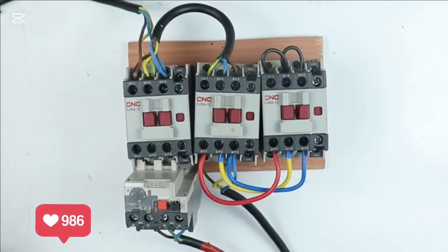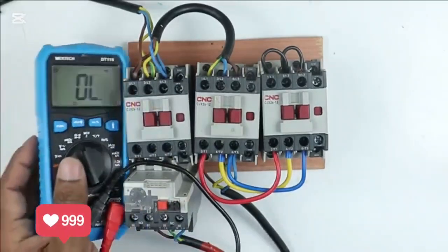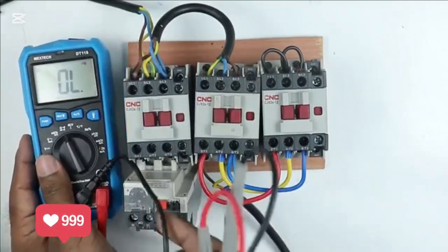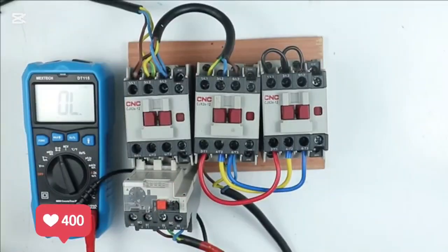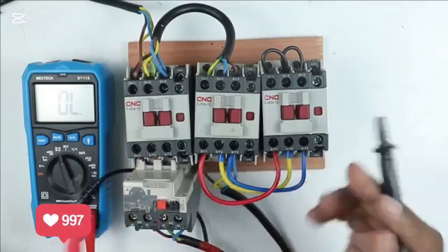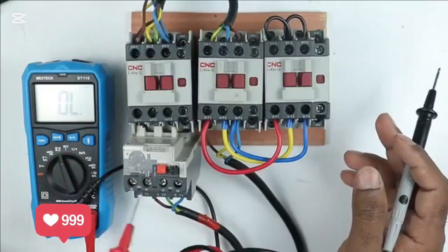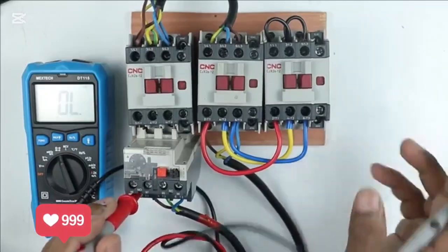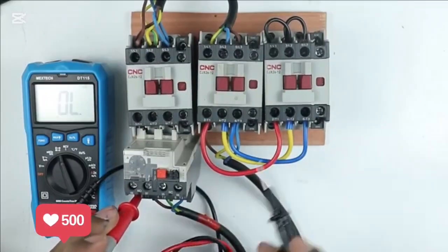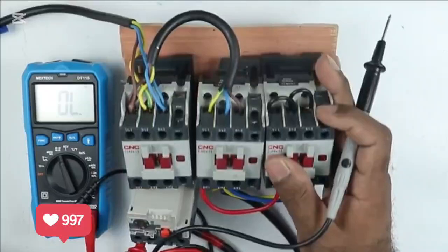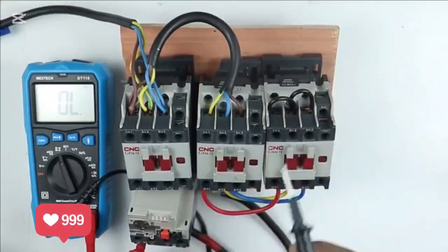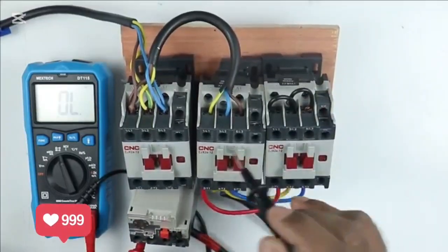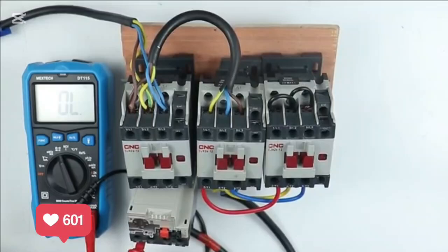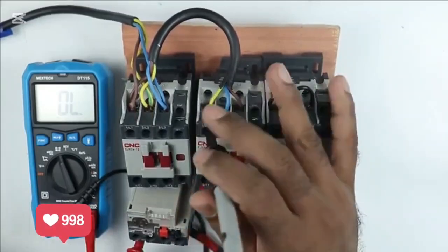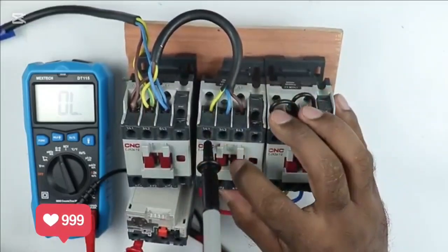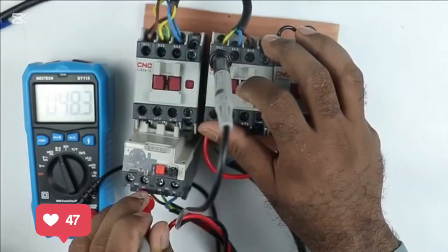For checking the connections, what you have to do, take this multimeter and set this multimeter to continuity position. After setting this to continuity position, take one probe of multimeter and connect this probe to this overload relay at output terminal. Now the power supply that comes from here is going to which point, you have to check this. For this, we have to turn on the contactor. Along with this, we have to check the continuity. With this terminal, I connected probe and turned on this contactor manually. Here I am getting the continuity.